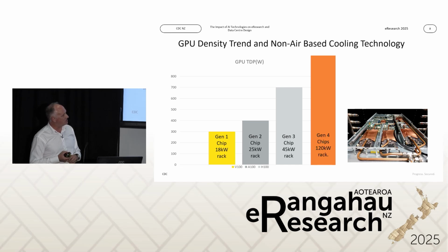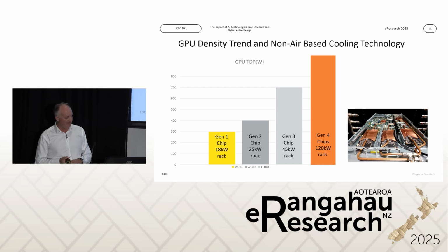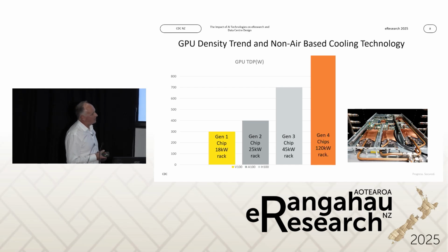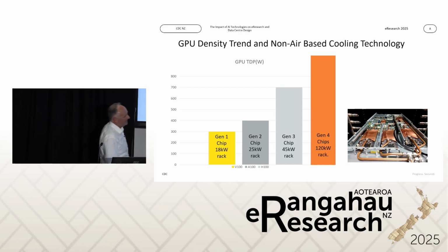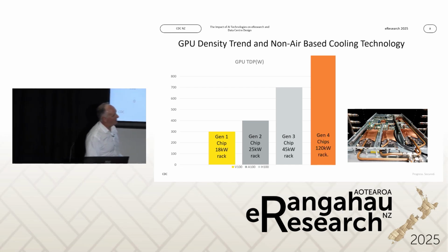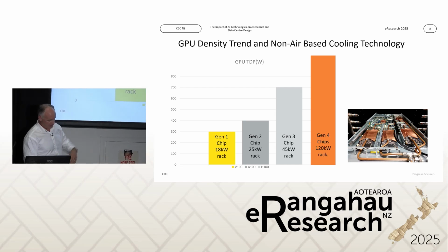The latest generation of chips - and this has been around in supercomputing for many years - we're basically getting rid of those air-cooled heat sinks on the processors. We're connecting cold plates instead. You've seen this in supercomputing and gaming for a while. Essentially what you're doing is putting that cold plate directly onto the chip, getting rid of the massive air-cooled heat sink, and running a glycol mix or similar through those chips.